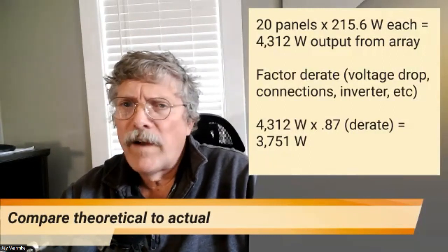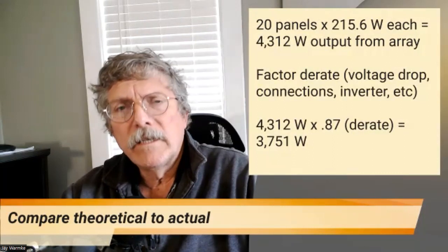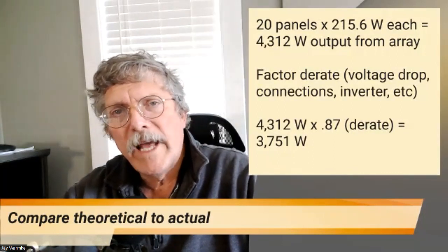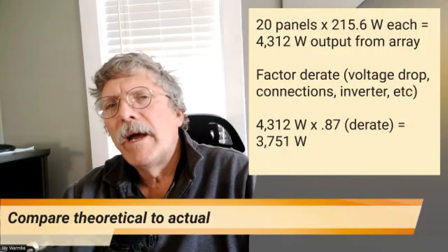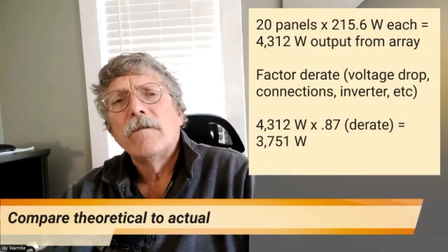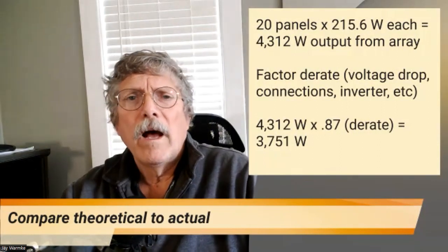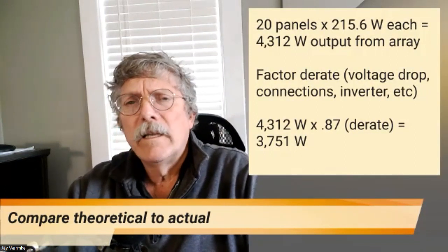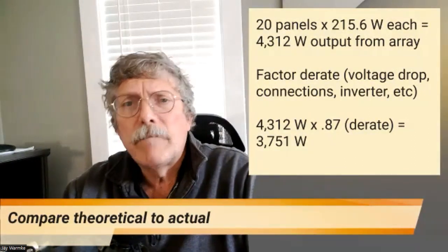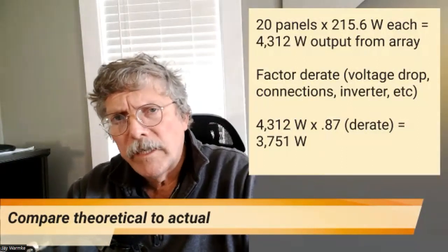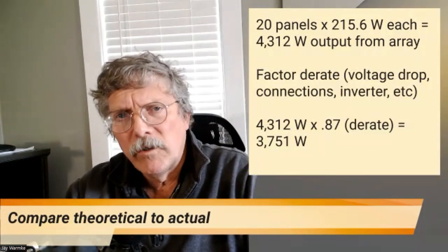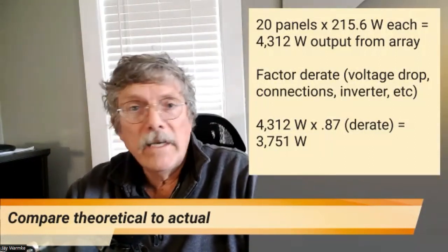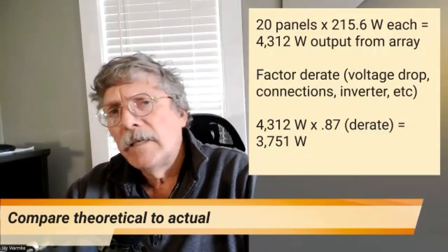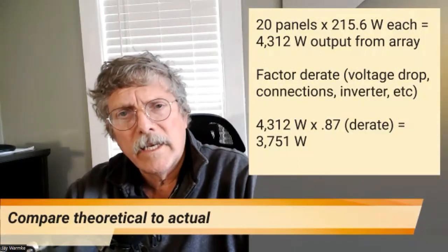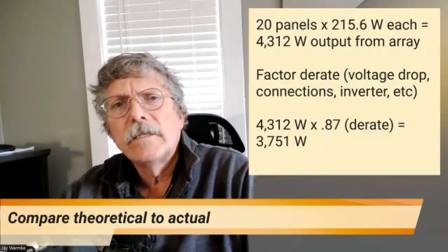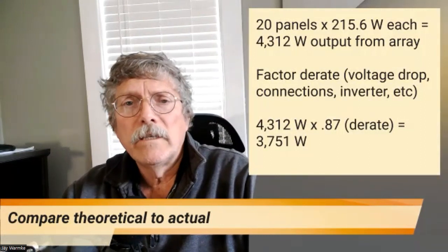Today's inverters, we often find, are only going to lose 2 or 3%, but it's still something you've got to account for. So, for instance, you might have 2.5% from voltage drop and connections. You might have another 3% from your inverter. Then there's, of course, when you're putting strings together, mismatch of panels. If it's plus or minus 5%, then when you hook them together in a string, it's always going to produce at the lowest common. So that's going to be minus 5%, which is one of the reasons why optimizers are a good thing, or any of those electronics that get connected there, is you avoid that loss due to lowest common production value.